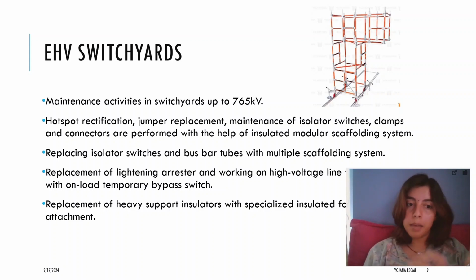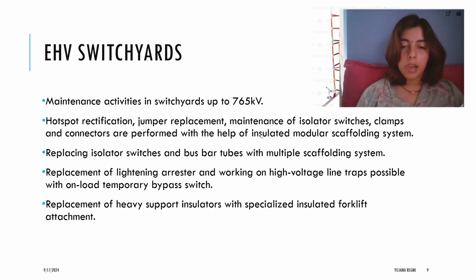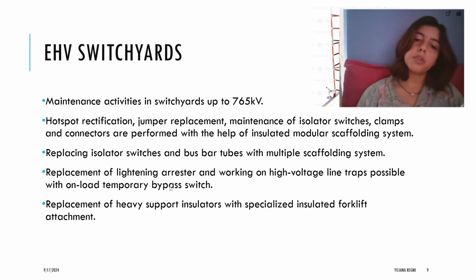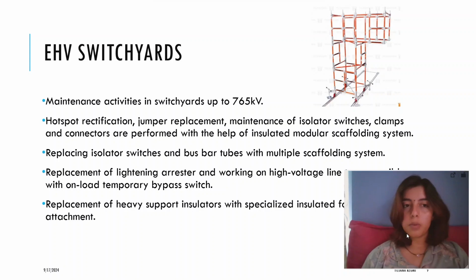We can tighten the clamps and connectors. Bus bar tubes can be replaced, and even lightning arresters. We can work on high voltage line traps with an on-load temporary bypass switch. Heavy support insulators can be replaced with a specially insulated forklift attachment. So there is a lot of equipment we can use while working on switchyards that are still energized.